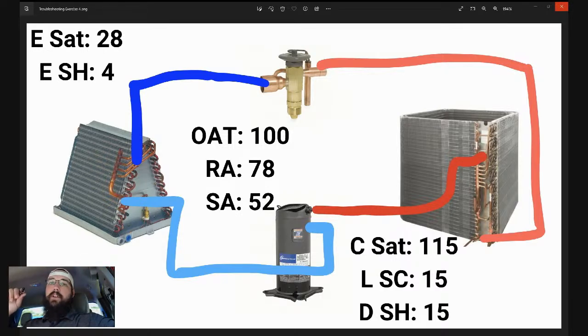So I think our issue there is we could rule out the bulb issue. Now we could do an inspection. We look at it, we're fine with that. But just using our readings, our superheat and our saturation are too low for what I would expect to see with an improperly mounted bulb. Yeah, math is hard.